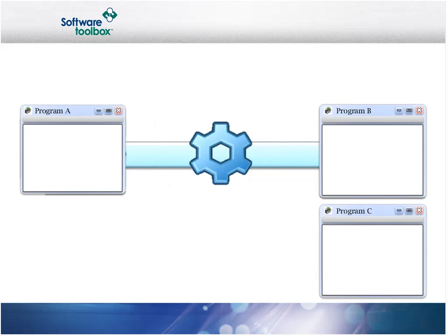The data hub acts as more than just a conduit for data, though. It also acts as a mirror of the data from remote OPC servers back to your local client machine. That means a single tunnel can support any number of clients on each side of the tunnel, and the data flows across the tunnel only once, yet as you can see, serves multiple clients. This can greatly reduce bandwidth usage across slow networks.